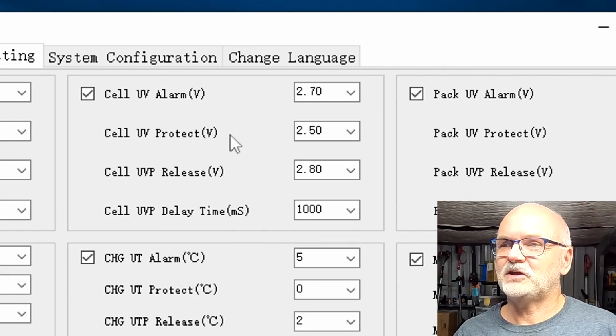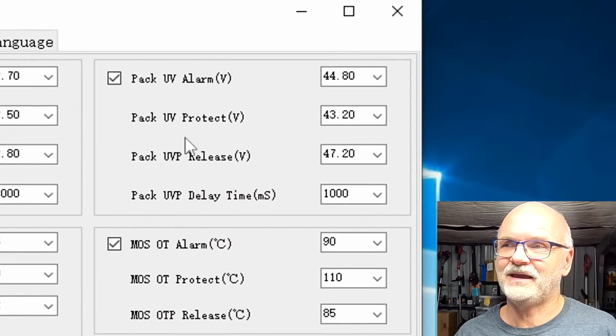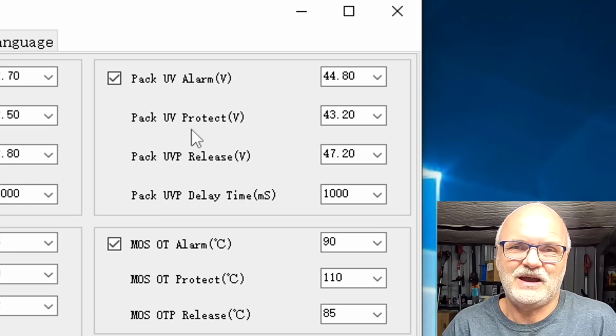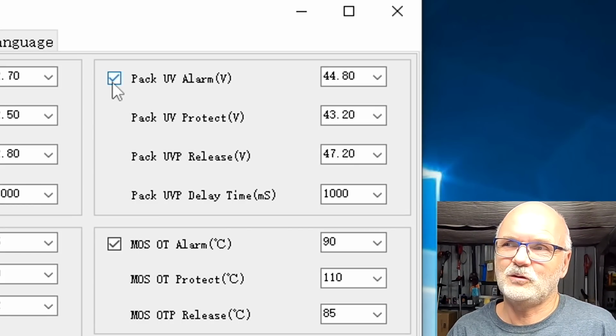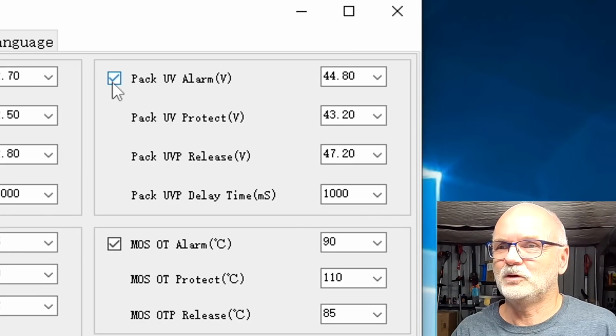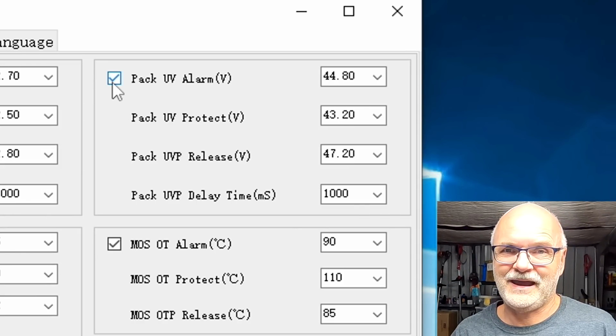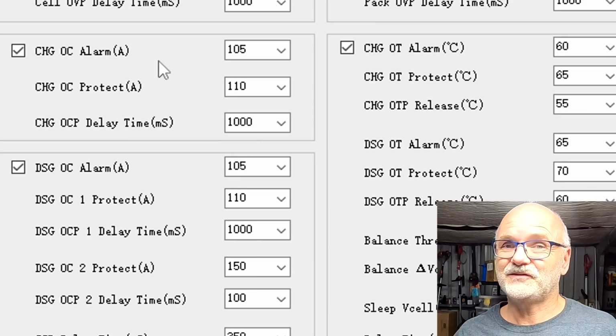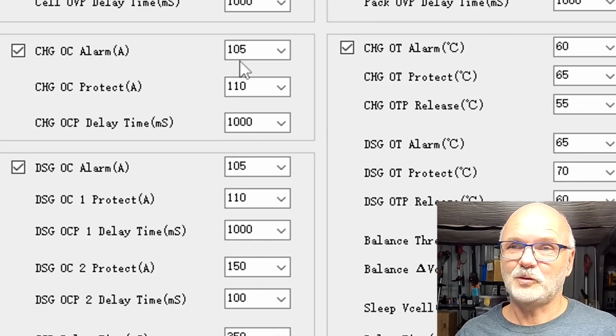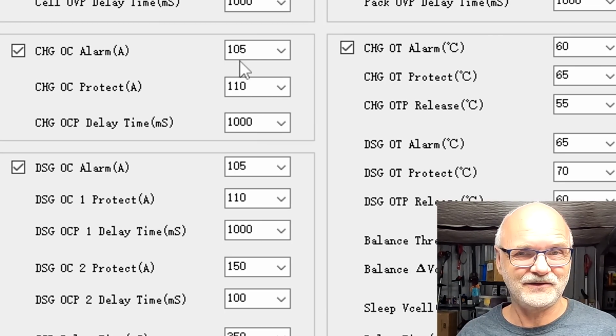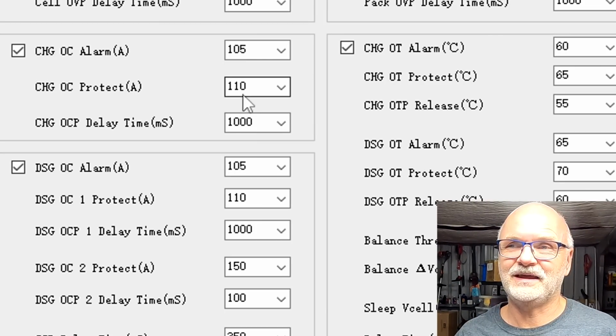The undervoltage protection kicks in at 2.5 volts. This is fine. And again, we have got a Pack undervoltage protection here, which I found totally useless. So in theory, we can disable the undervoltage and overvoltage protection and alarms for the Pack level. And this is a 100 amp BMS. So we're getting an alarm at 105 amps, which I think is a bit too high. I would like to see the alarm at around 90 amps. And protection kicks in at 110.